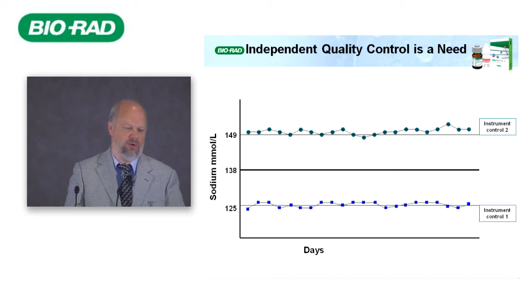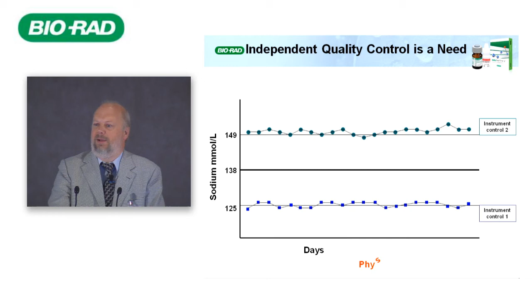Independent quality control for me is absolutely necessary. Here I brought an example from one laboratory. They do sodium measurement, and they use the instrument control fluid over time, and it looks very nice. The high control and the low control fit very well to their limits, and they are very happy about this. But unfortunately, they got a phone call from the physician, and the physician told them that he is not happy with the sodium results. They are too high. Well, we have nice quality control. Both are very well within the limits. So there is nothing wrong in the laboratory. There might be something wrong with the drawing of the sample or whatever the physicians are doing.